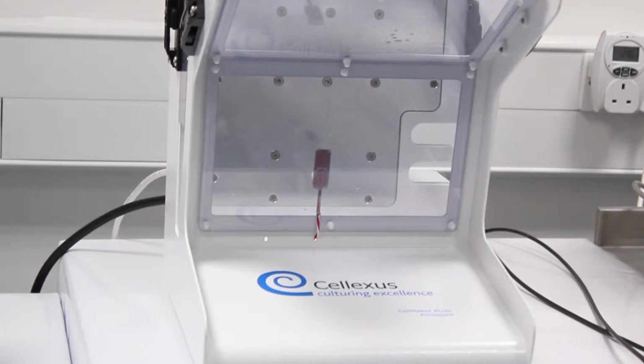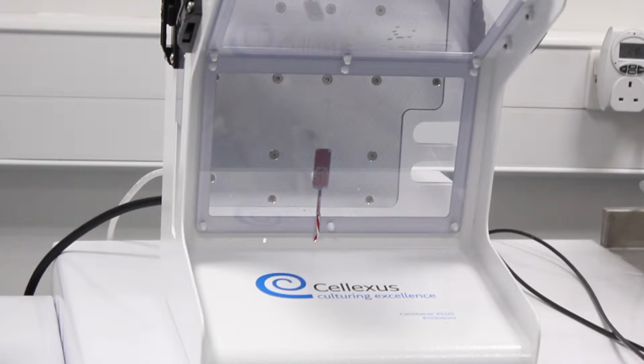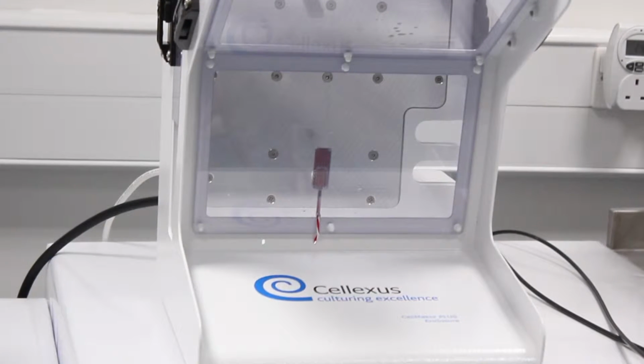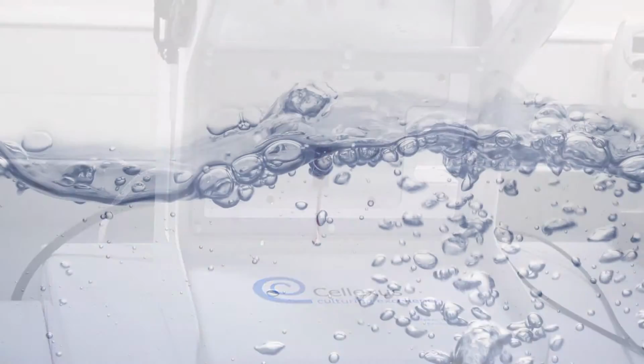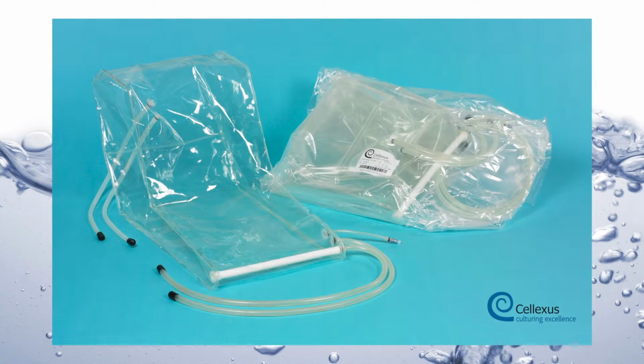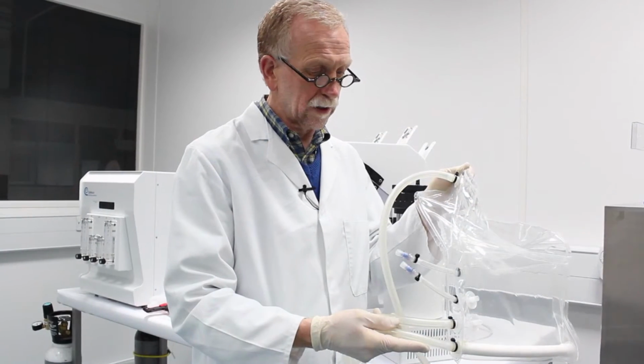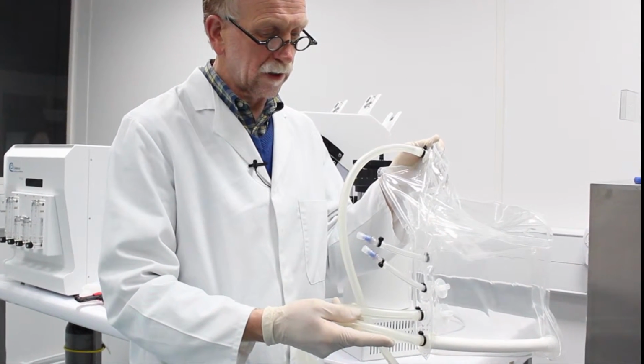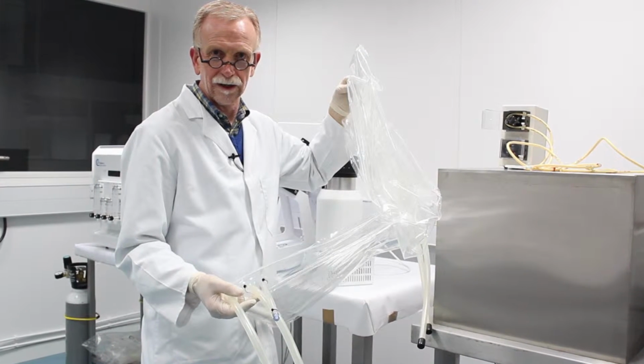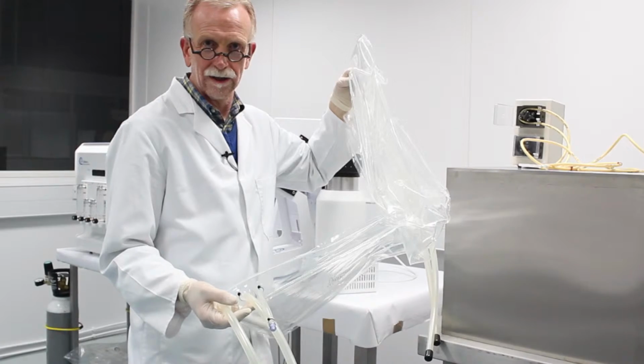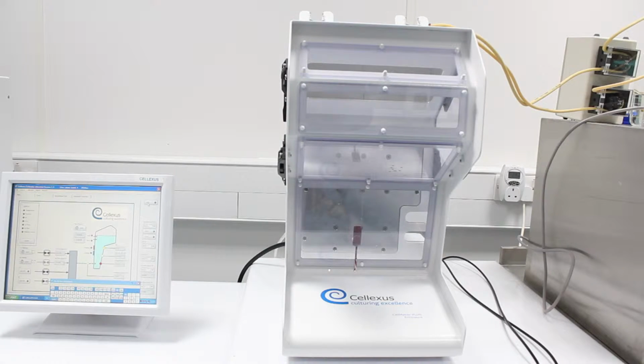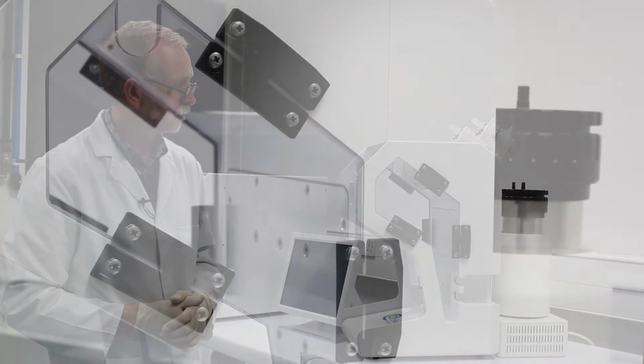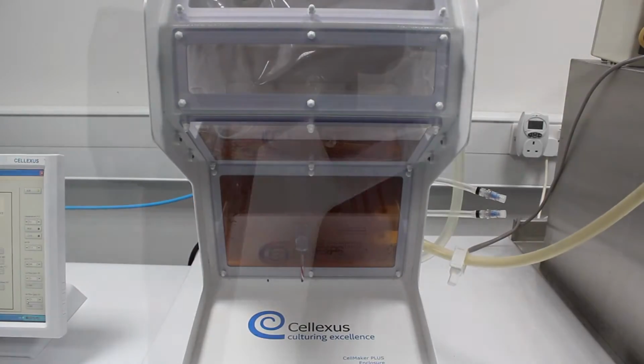The Cellmaker Enclosure incorporates a Peltier-driven thermal plate and temperature sensor to enable the cell culture temperature to be closely monitored and controlled. The enclosure comes in 8 litre and 50 litre sizes for use with the 8 litre and 50 litre Cellmaker bags respectively. The 8 litre enclosure can operate from 1 to 8 litres and the 50 litre enclosure can operate from 10 to 50 litres to provide scale flexibility.